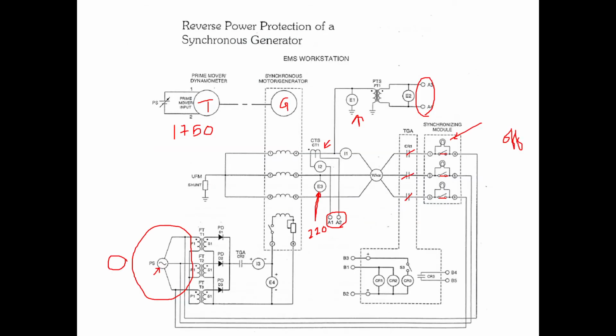So let us go back to the previous circuit. Here you can see CR1 and CR2. Under normal conditions CR1 and CR2 are energized. Energized means this contact is closed and this contact will also be closed. So this is the normal condition.